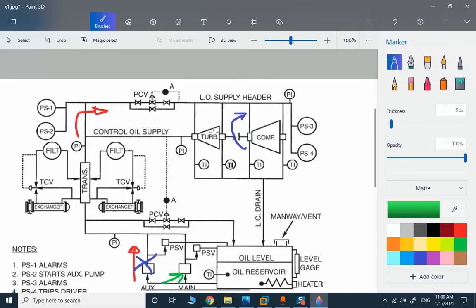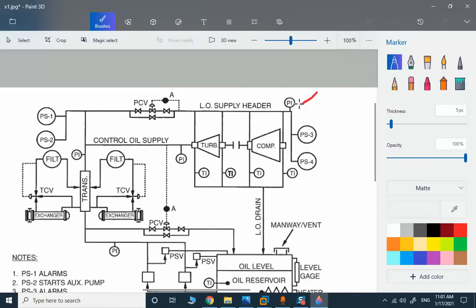The most important part of our function test here is one of these pressure transmitters. Oil pressure is very critical for our case. If we lose the oil pressure here it means that the oil system is blocked or there is some leakage somewhere — oil leakage, or oil level is not sufficient, or there is a problem with one of these filters — and the oil pressure is not sufficient.